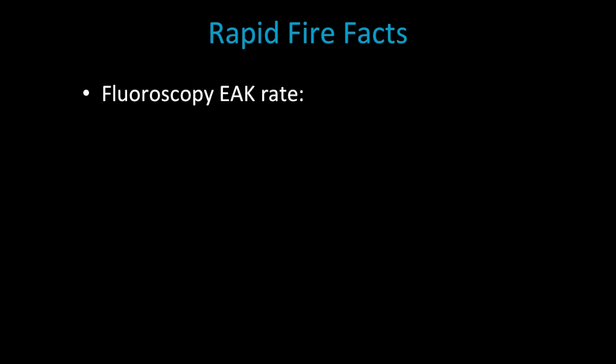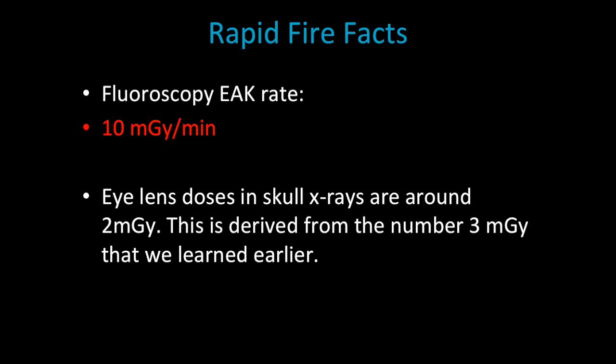The fluoroscopy air kerma rate is 10 milligrays per minute, and that's a rate and you should know that number. The eye lens dose is about two milligrays for a skull radiograph. Remember we said for an abdominal radiograph we have three milligrays delivered, and when we go to a skull radiograph and we calculate the eye lens dose, it's going to be in the range of two milligrays.